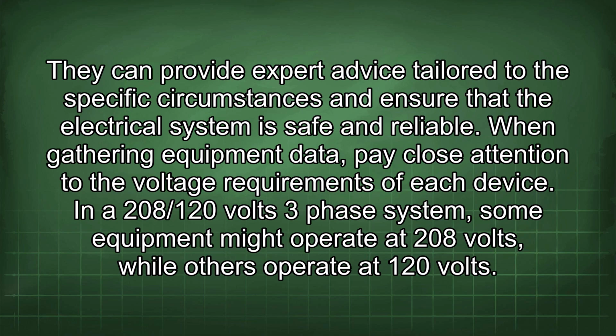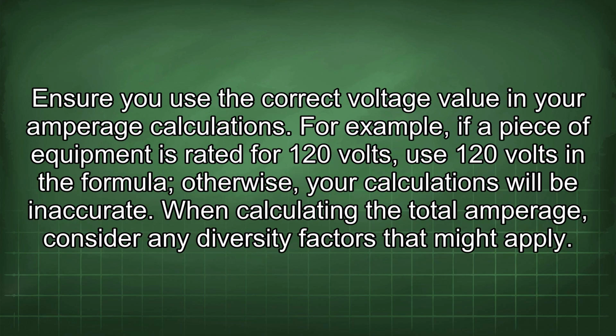When gathering equipment data, pay close attention to the voltage requirements of each device. In a 208/120 volts three-phase system, some equipment might operate at 208 volts, while others operate at 120 volts. Ensure you use the correct voltage value in your amperage calculations. For example, if a piece of equipment is rated for 120 volts, use 120 volts in the formula, otherwise, your calculations will be inaccurate.